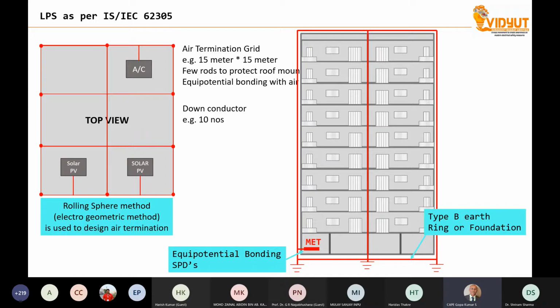And in addition, we have to make equipotential bonding. Equipotential bonding means the mesh and the metal parts of these electrical apparatuses are interconnected. This is the normal way of doing air termination. Now, for designing the air termination and positioning the rod, we also have the electrogeometric sphere principle, the rolling sphere method, which has been followed across the globe for several years, especially for transmission lines and distribution lines. Millions of kilometers of transmission lines across the globe are designed with this particular principle, rolling sphere electrogeometric modeling.